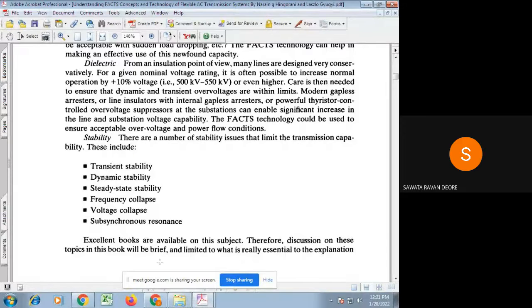In view of keeping this synchronous operation under steady state as well as transient, the power angle curve is utilized. That is the P versus delta curve. The peak of this curve is called the maximum power handling capacity, P max, which is equal to the magnitude of the sending end voltage times the magnitude of the receiving end voltage divided by the reactance of the transmission line. From this power angle curve, we come to know that power varies positively with delta for load angle delta between 0 to pi by 2, whereas from pi by 2 to pi, that is 90 to 180 degrees, the P versus delta relation is negative, meaning with the increase in delta, electrical output goes on decreasing.